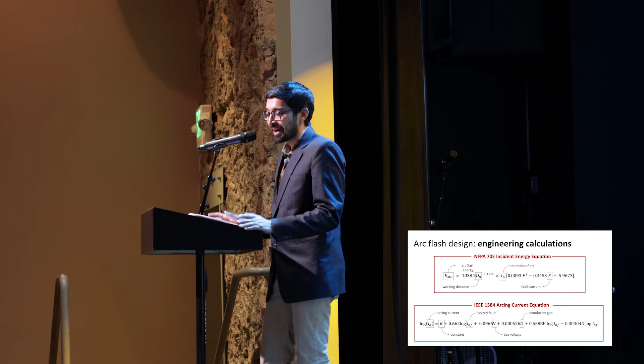2 standards are here: NFPA 70E and IEEE 1584. They're very helpful because NFPA tells you what kind of PPE to wear, and IEEE 1584 tells you how to actually calculate incident energy and arcing current.